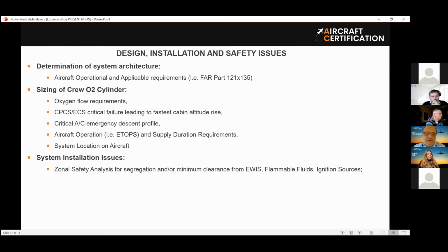So, segregation, minimum clearance from fluid, flammable fluid, and ignition sources. Air ventilation design: if you're in the pressurized compartment and all that oxygen content is discharged, you may have an oxygen enriched atmosphere. That's a big issue, because whenever you have oxygen, normally we have 21% oxygen content in the ambient air. Transport Canada says anything above 23% oxygen concentration is already a fire hazard. So either we put the oxygen in a place with no ignition sources, or we provide some kind of ventilation system to dilute and dissipate that oxygen.